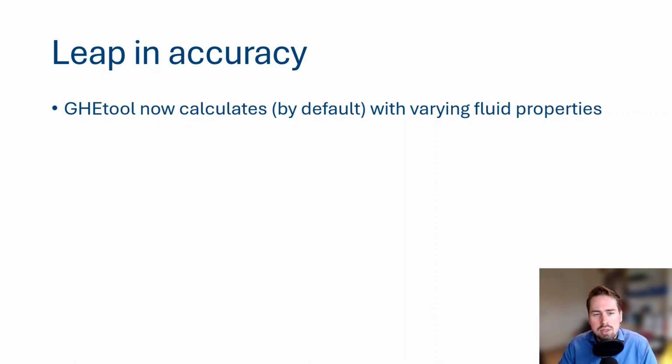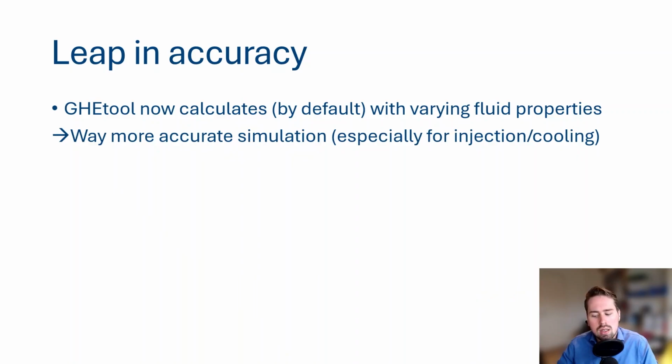Now, why is this important for you? It is important because we will now calculate way more accurately how your fluid behaves in the ground, and especially for injection and cooling with these higher temperatures, which also have a higher Reynolds number and hence a better borehole thermal resistance.